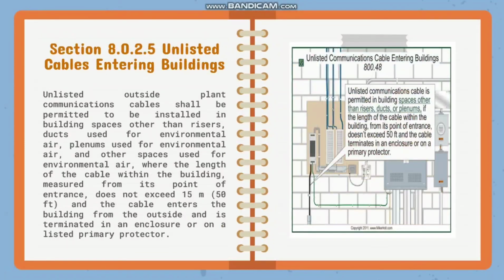Next section naman po is section 8.0.2.5, unlisted cables entering buildings. Unlisted communication cable is permitted in building spaces other than risers, ducts, or plenums if the length of the cable within the building from its point of entrance doesn't exceed 50 feet and the cable terminates in an enclosure or on a primary protector. So, unlisted cables are used by utilities and others for cable outside, as the unlisted cable has not been evaluated for smoke and flame spread. Pero, kagaya po ng sabi dito, permitted naman siyang gamitin in building spaces kapag yung length niya ay less than 50 feet and naka-terminate sa enclosure or primary protector.